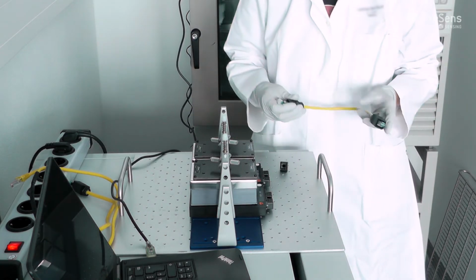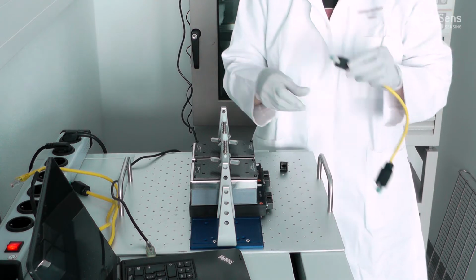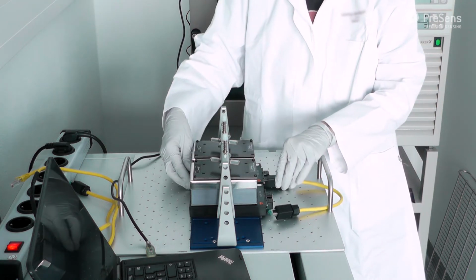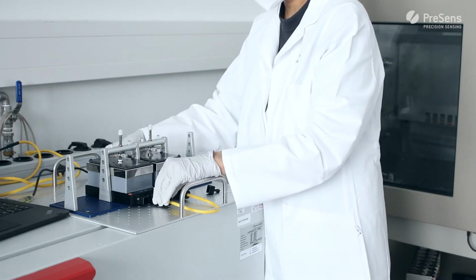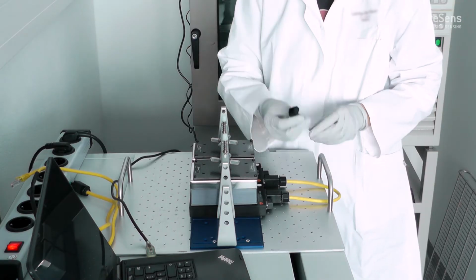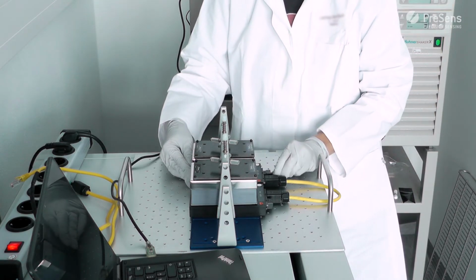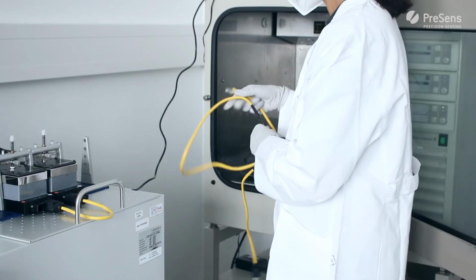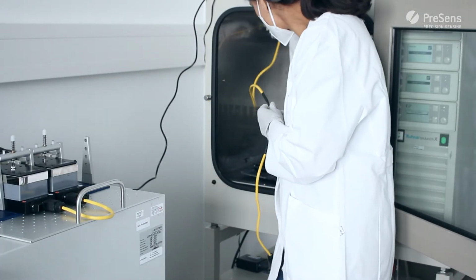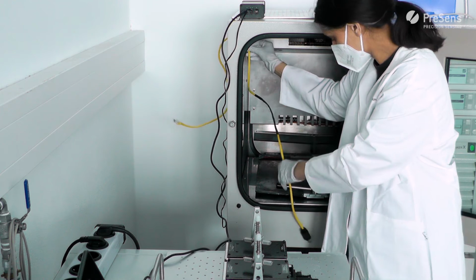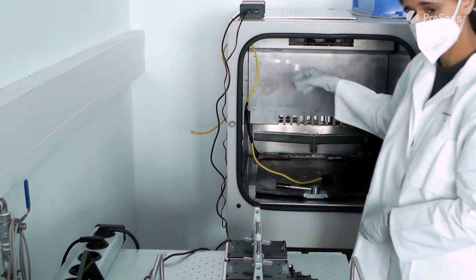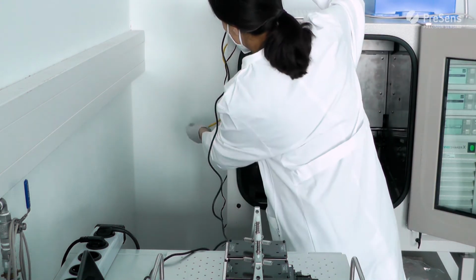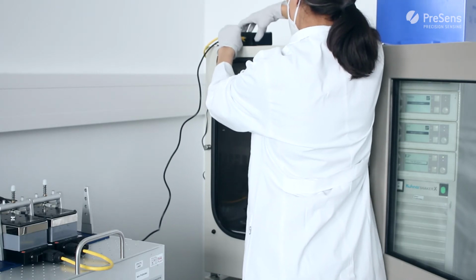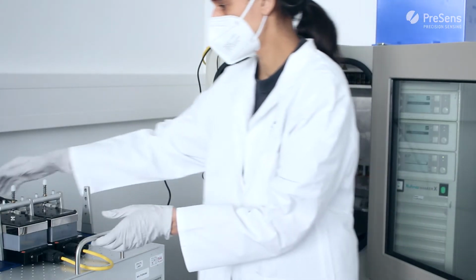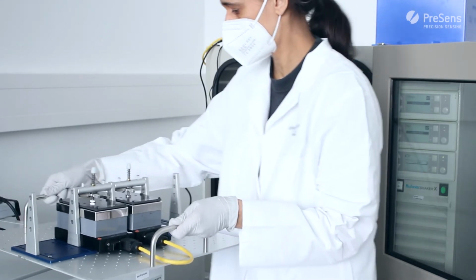Connect the SDRs with the short cable. And do not forget to close the last connector with the end cap, so no humidity can enter the reader and damage it. Use a port to lead the connection cable for the splitter outside. Place the tray with the clamp system in the shaker and connect the splitter cable to the SDRs.